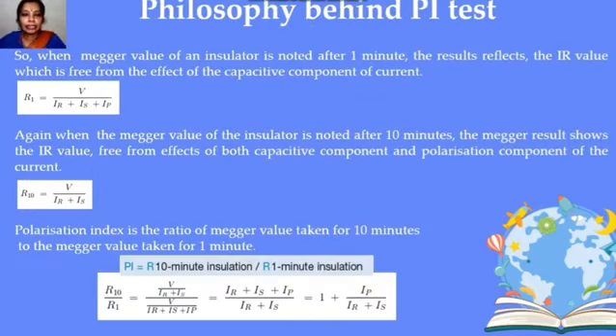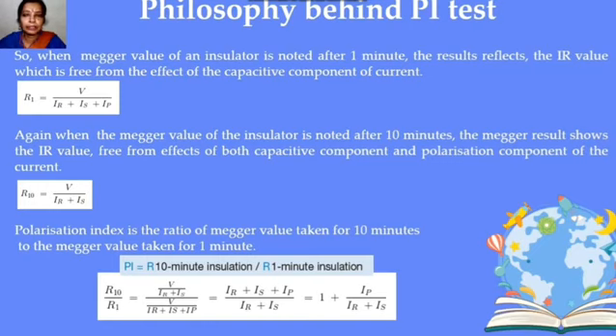When the insulation resistance value is noted after 1 minute, the resistance R1 is given by V divided by (IR + IS + IP). If measured after 10 minutes, R10 is given by V divided by (IR + IS). The first value is termed R1 (at 1 minute) and the second R10 (at 10 minutes).